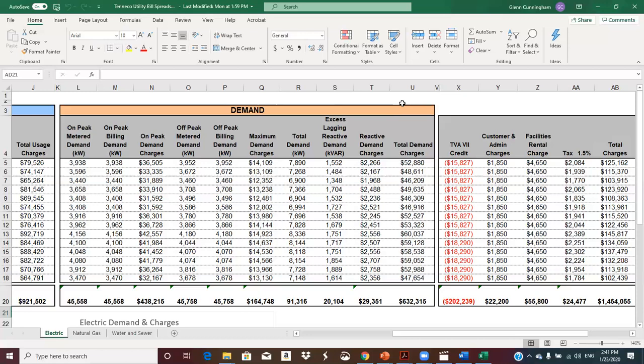So when you put in these capacitors, you have to do a study where you monitor this over time, and you see how it jumps around because during operation you start and stop stuff all day long, and it jumps up and down. So what you do is calculate, well, the most capacitors I would need is this, but I need to be able to switch it. Say maybe I'm going to put in 2000 kVAR, but I'll put in a switching bank. The controls on the capacitors monitor the power factor, and maybe you're switching 300 kVAR blocks in and out of the circuit all the time to keep you from going too far. Because if you put all 2000 in all the time, you'll drive it into leading most of the time, or half the time.